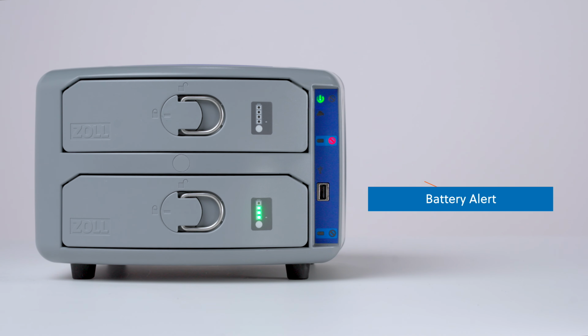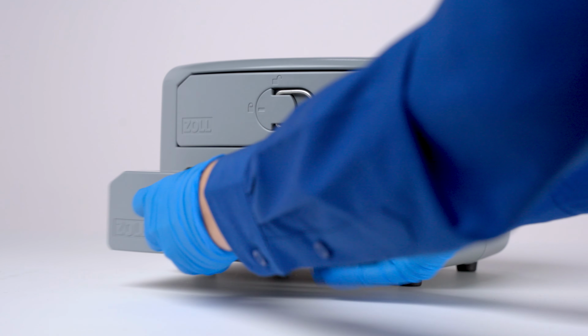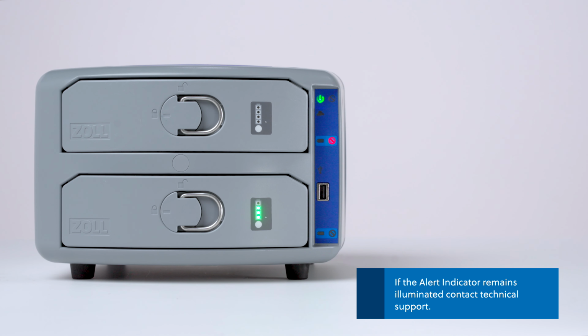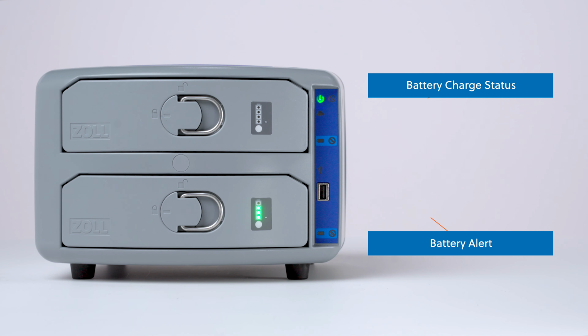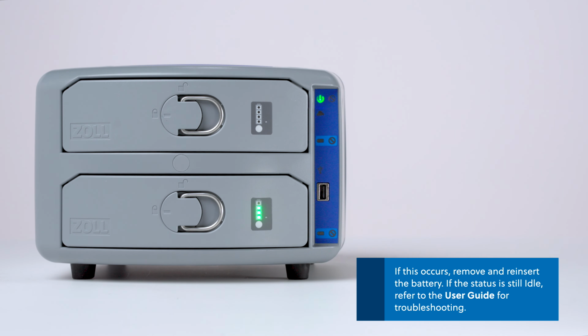If the battery alert indicator illuminates, note that the battery charger was unable to charge the battery, or the battery has failed the measurement cycle. If this occurs, remove and reinsert the battery into the charger. If the alert indicator remains illuminated, note the battery serial number and contact technical support. If neither the battery charge status indicator nor the battery alert indicator illuminates, the battery charger is unable to recognize the battery. If this occurs, remove and reinsert the battery. If the status is still idle, refer to the user guide for troubleshooting.